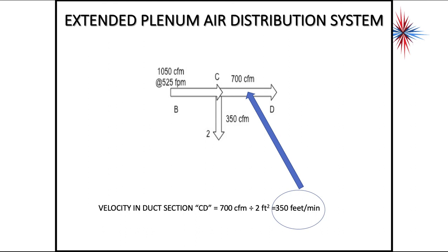Here, velocity in section C to D, we now are only left with 700 CFM, because we've taken off the 350. So 1,050 minus 350, I only have 700 CFM. So here, we have 700 CFM divided by the 2 square feet gives me a velocity of 350 feet per minute.